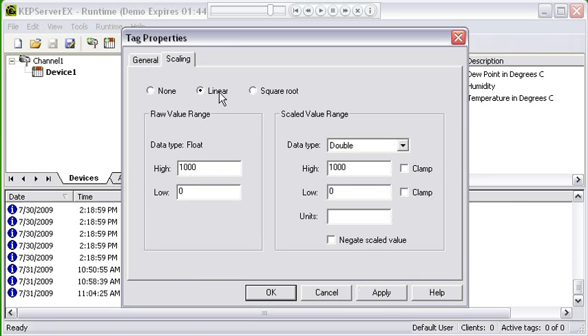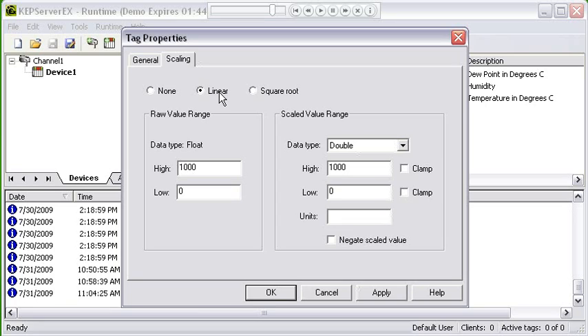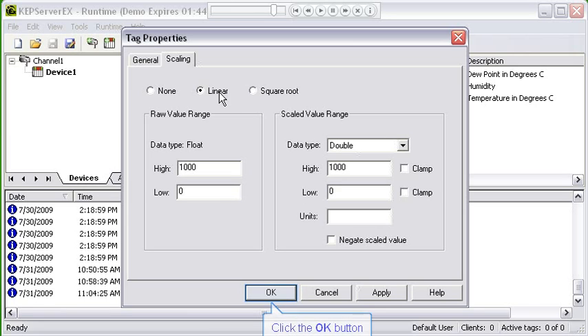The last setting here is negate value, and that allows us to literally multiply the scale value by negative one. We're starting to see devices now that might have a raw value of 0 to 500 and they need to show a scale value of 0 to minus 50. So you would set up your normal linear scaling and then you would check this negate scale value, and it literally multiplies the scale value result by negative one.